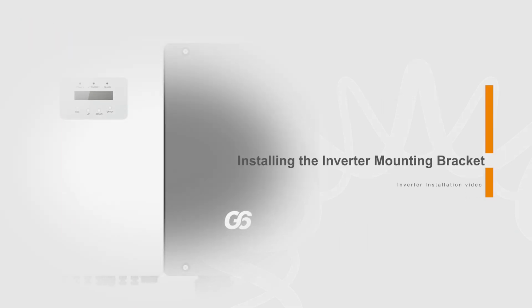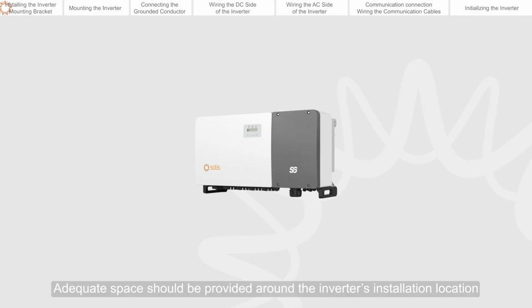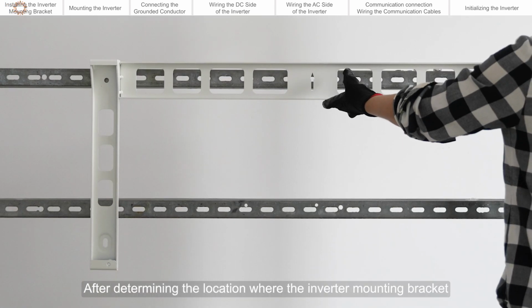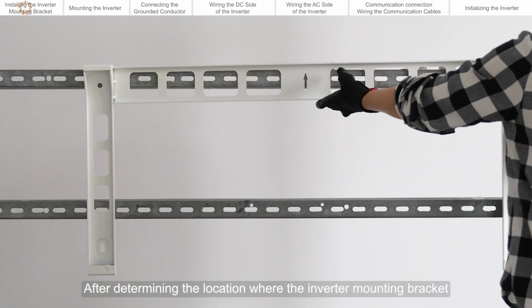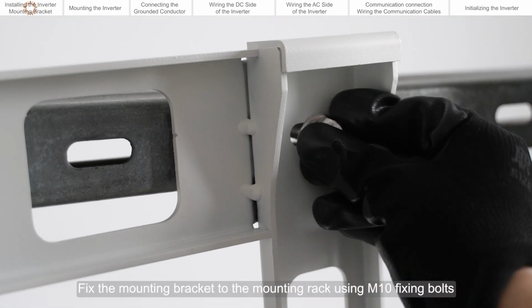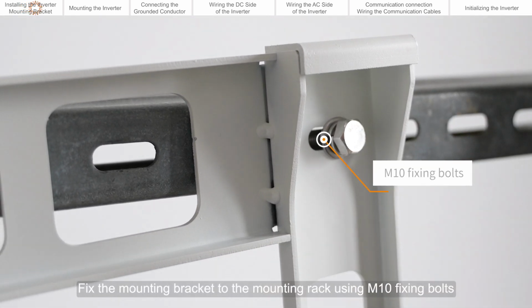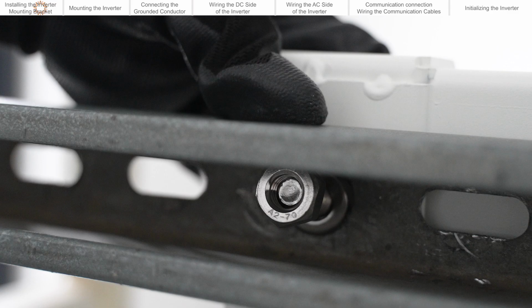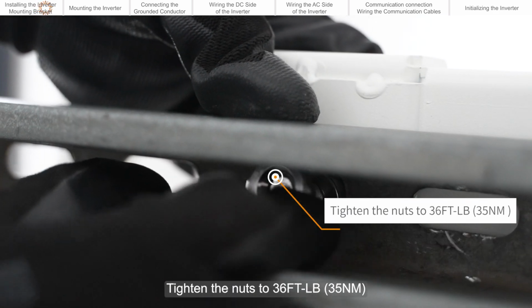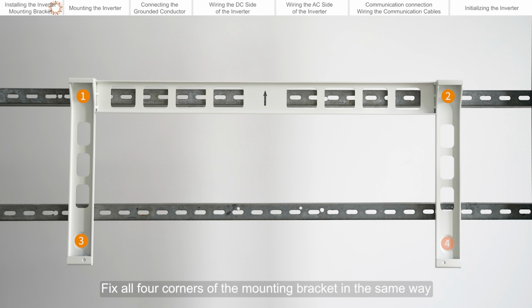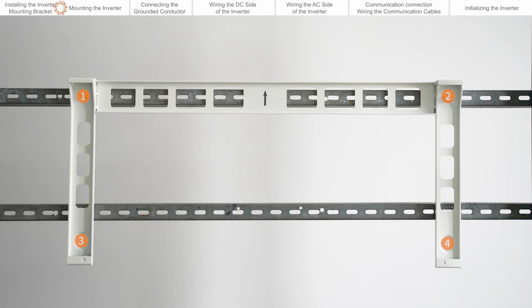Installing the inverter mounting bracket. Adequate space should be provided around the inverter's installation location. After determining the location where the inverter mounting bracket will be installed, fix the mounting bracket to the mounting rack using M10 fixing bolts. Tighten the nuts to 36 foot-pounds, 35 newton-meters. Fix all four corners of the mounting bracket in the same way.